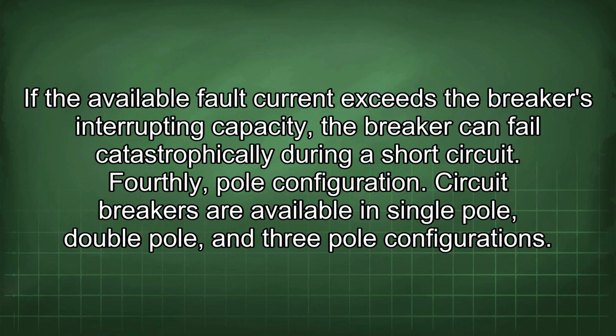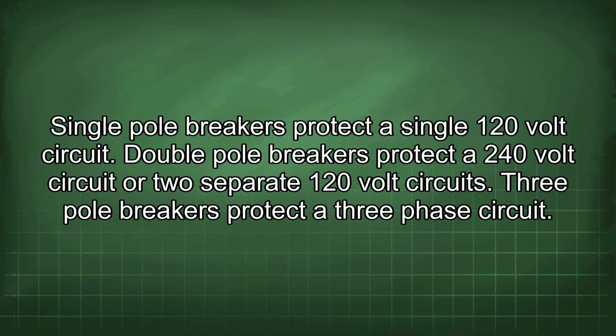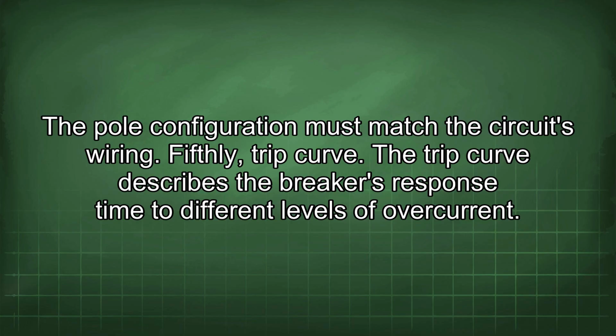Fourthly, pole configuration. Circuit breakers are available in single pole, double pole, and 3-pole configurations. Single pole breakers protect a single 120 volt circuit. Double pole breakers protect a 240 volt circuit or two separate 120 volt circuits. 3-pole breakers protect a 3-phase circuit. The pole configuration must match the circuit's wiring.